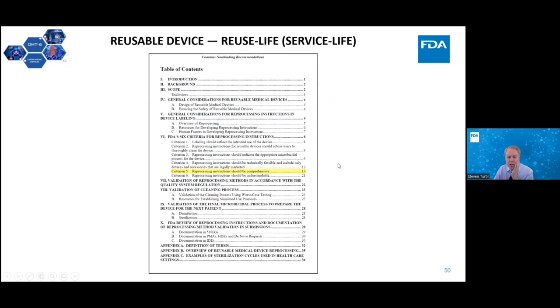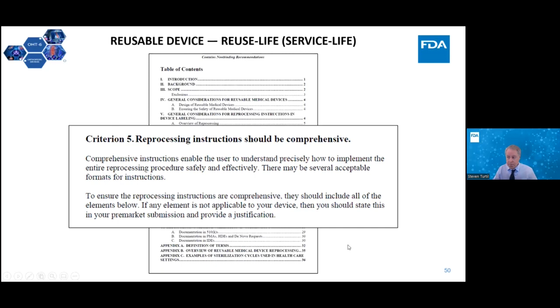So what we're going to look at is only criterion 5, reprocessing instructions should be comprehensive. And when we take a close look at that, comprehensive instructions enable the user to understand precisely how to implement the entire reprocessing procedure safely and effectively. There may be several acceptable formats for instructions. To ensure the reprocessing instructions are comprehensive, they should include all of the elements below. If any element is not applicable to your device, then you should state this in your pre-market submission and provide a justification. So I'm going to be jumping just to criterion number 5, item L, reuse life.